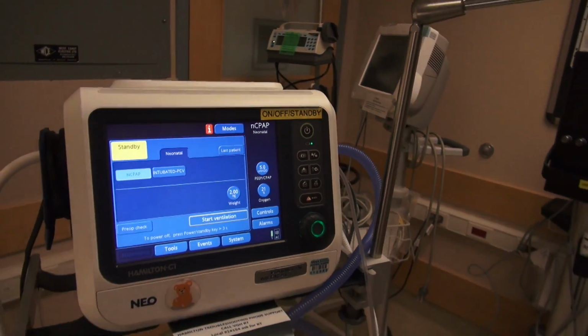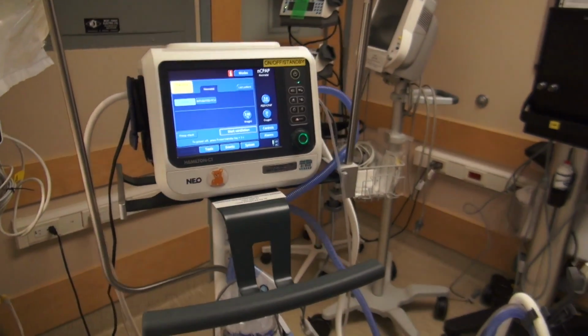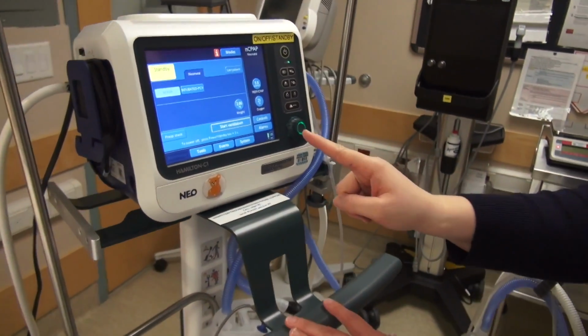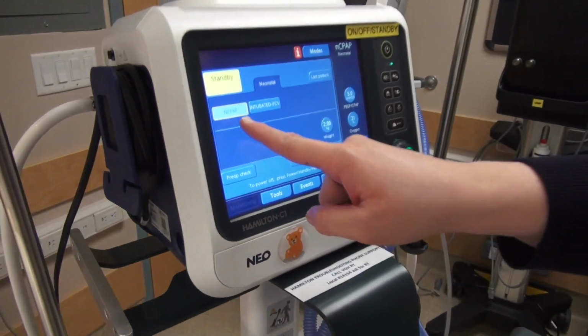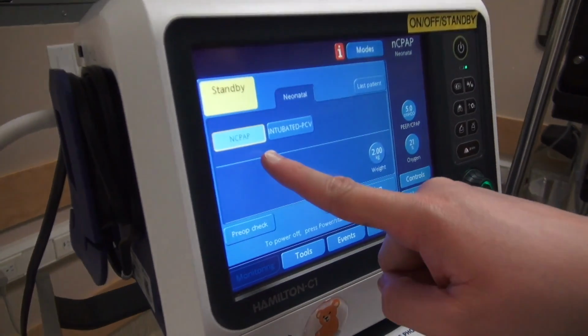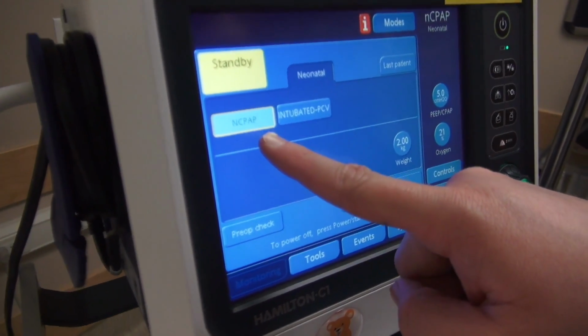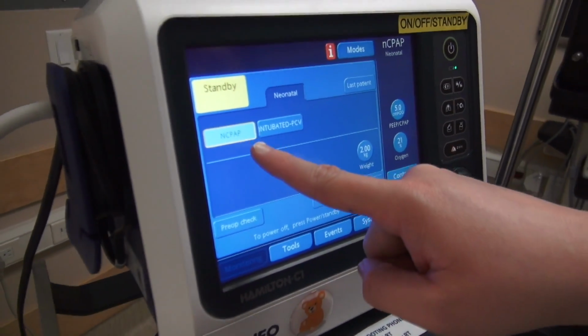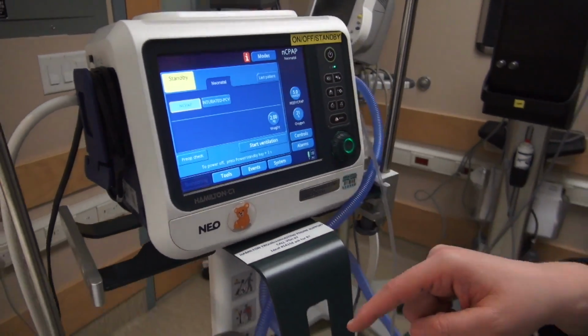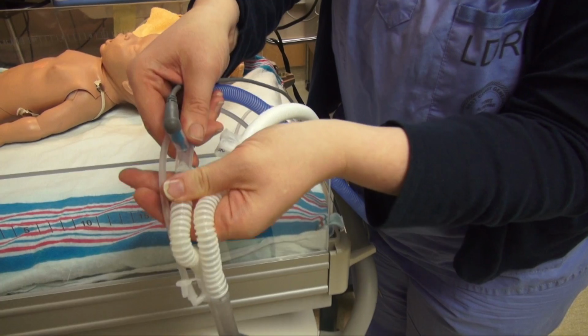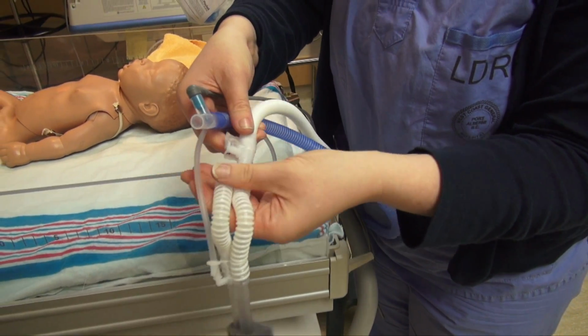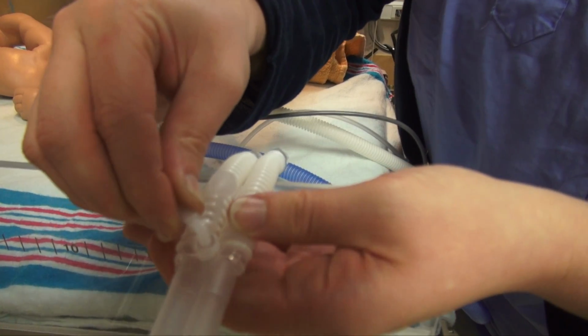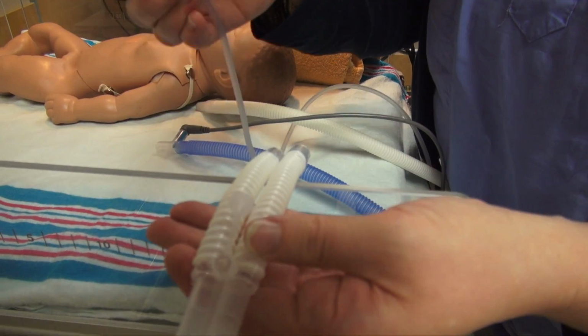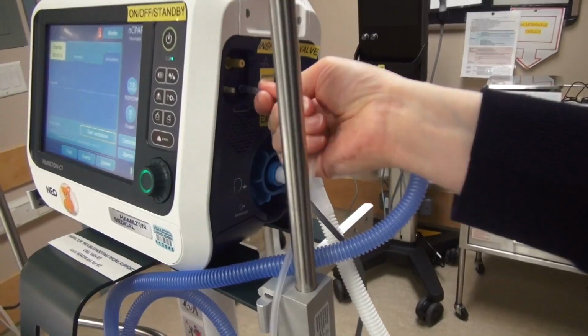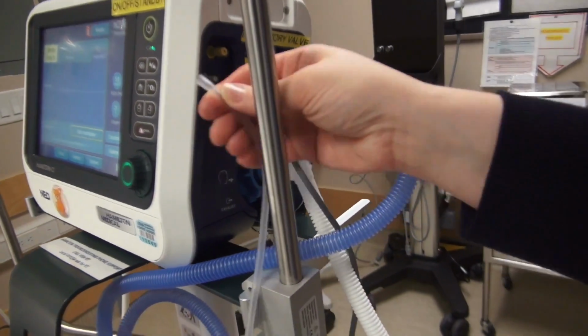Ventilator setup. Note, the Hamilton nasal CPAP ventilator will always be set up for nasal CPAP mode. The following steps are to switch it from nasal CPAP mode to function in ventilator mode. Step 1. Disconnect ventilator tubing from CPAP generator and remove pressure gauge tubing from side of ventilator.